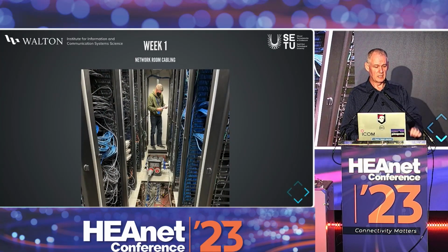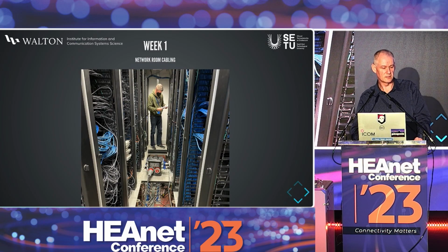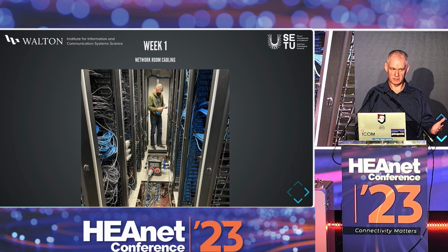So you can see there's a 64-amp or 63-amp distribution box on the ground, powering all the network equipment off of that. We had to figure out what we had to move, do a test, move equipment across onto it, and check that we were loading the phases on the generator fairly evenly.